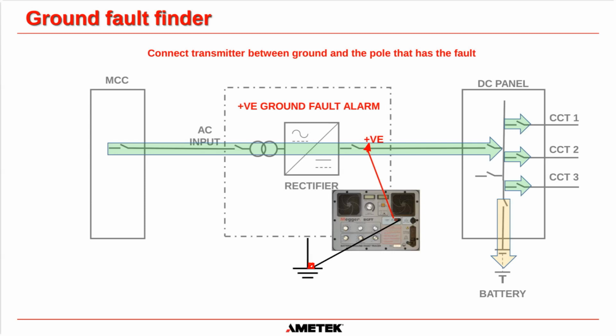Because what the signal generator does, there's a signal generator inside the BGFT, the battery ground fault tracer, and it creates a very low voltage, low current AC signal, and it injects that signal along the fault line. That signal needs a return path, so it will only travel from the positive down to the ground. So let's say the fault was in circuit three. It would have to flow all the way through circuit three and then get back down to ground that way. Okay?